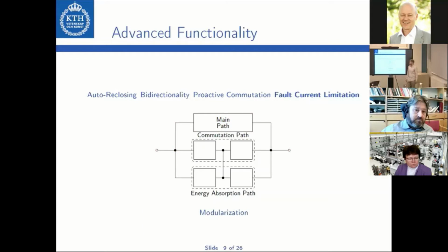Another interesting functionality is fault current limitation. To implement fault current limitation, the general DCCB structure must be modularized. In this illustration, you can see a general DCCB structure with modularized commutation and energy absorption path. Both the commutation path and the energy absorption path consist of two modules. One module in the commutation path is connected in parallel to one module in the energy absorption path, respectively.